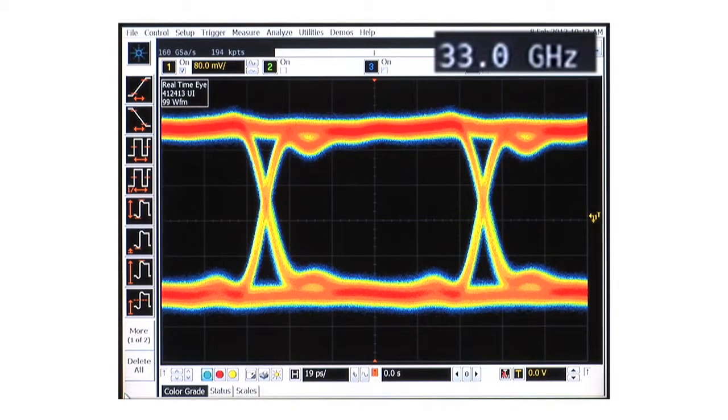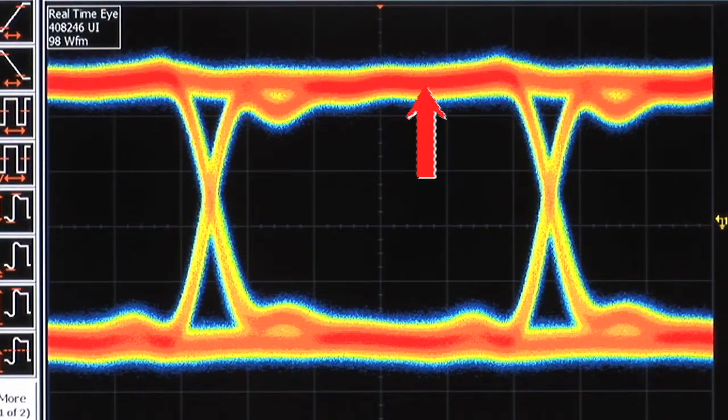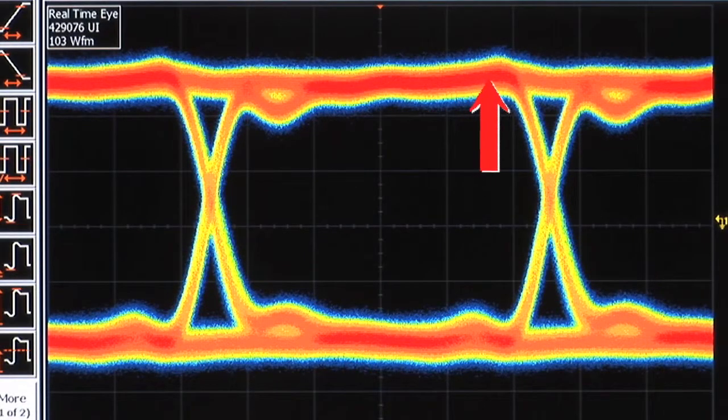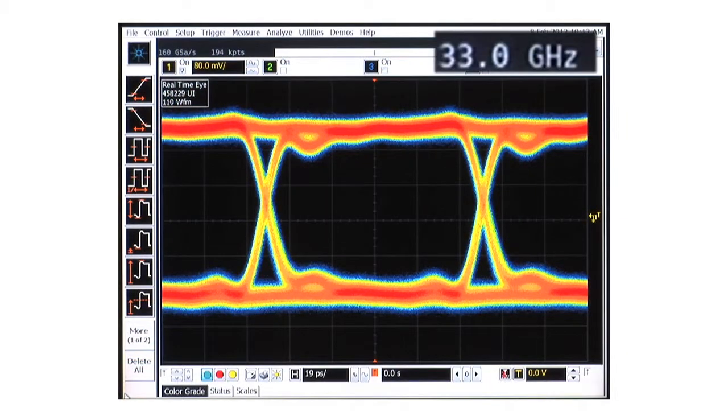At 33 GHz, the shape of the signal is now clear. However, there is still some ringing as even at 33 GHz, there's not enough oscilloscope bandwidth to capture this signal.